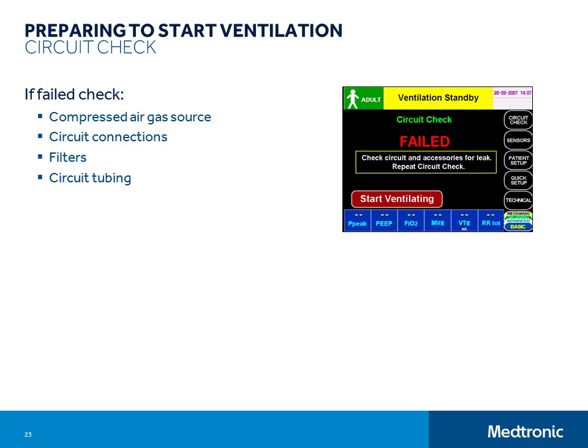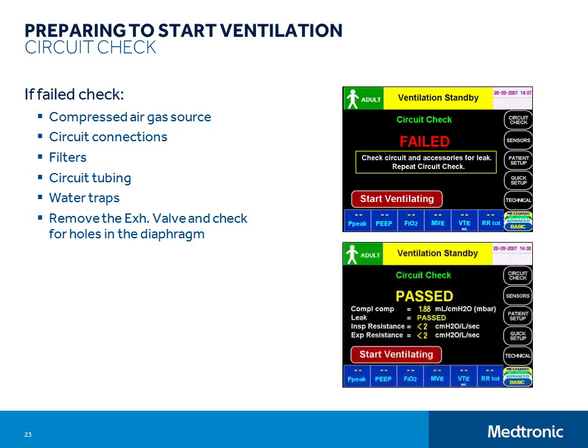If you have checked that there are no leaks in the breathing circuit and humidifier systems, and the circuit check still fails, then remove the exhalation valve assembly and check for holes in the diaphragm. As you can see, the Start Ventilating button is visible on all of these screens, so if necessary, you can start ventilating from any point in the ventilator setup process.